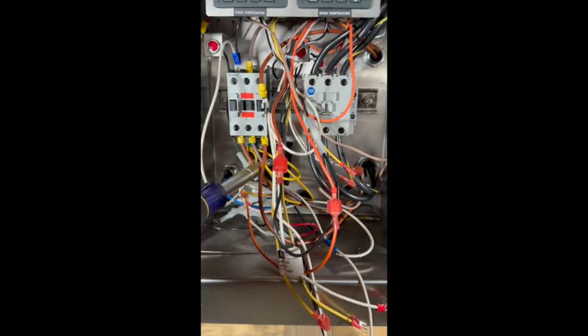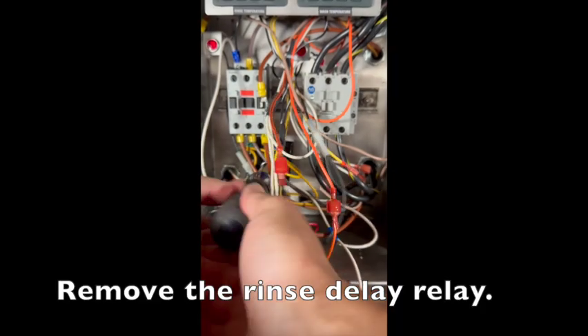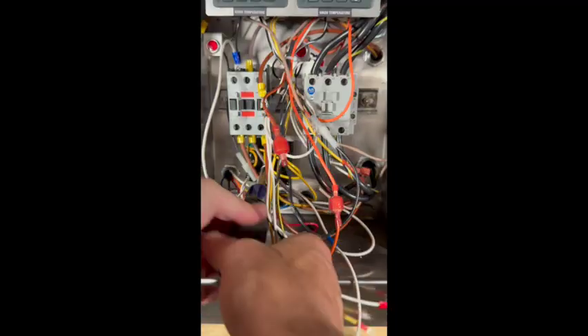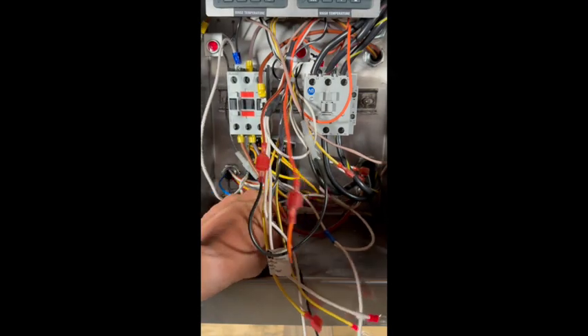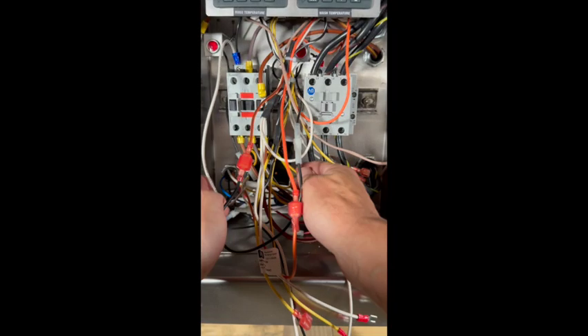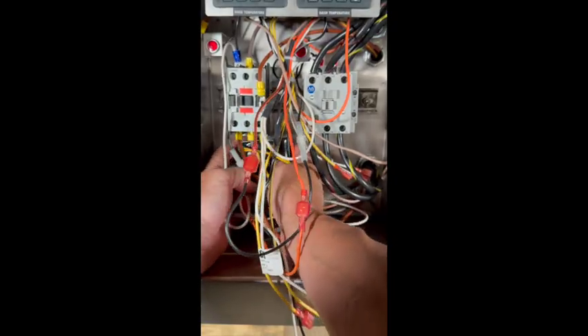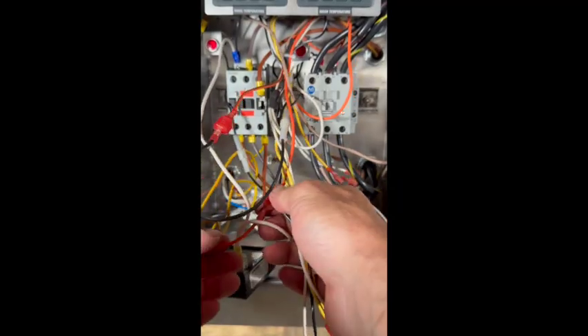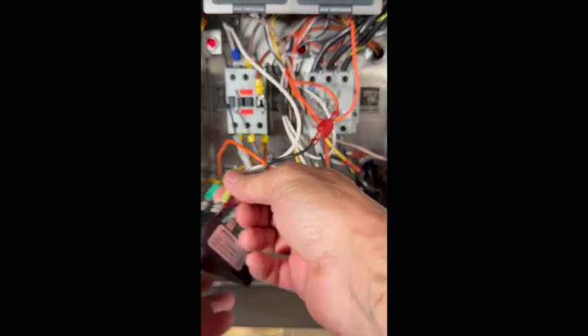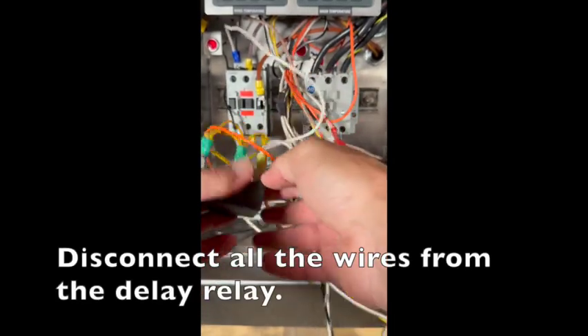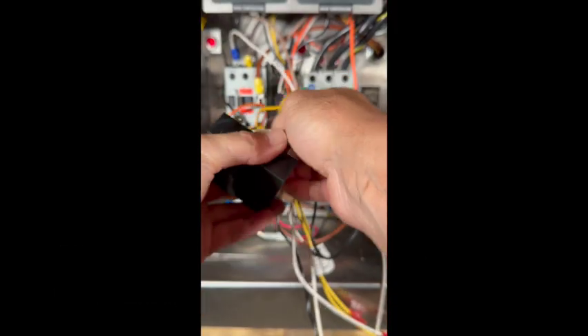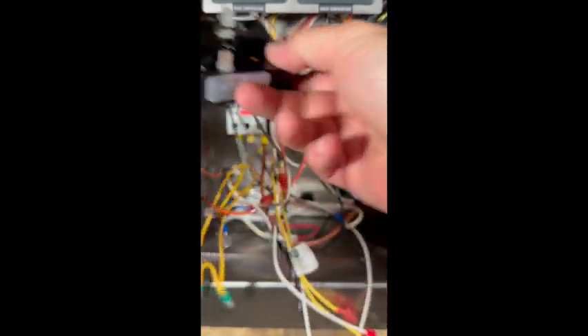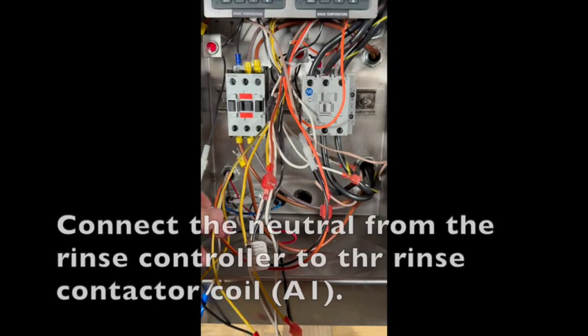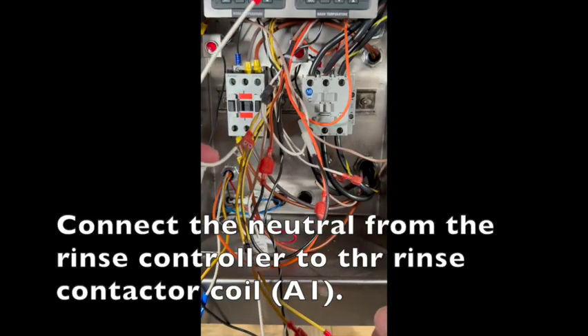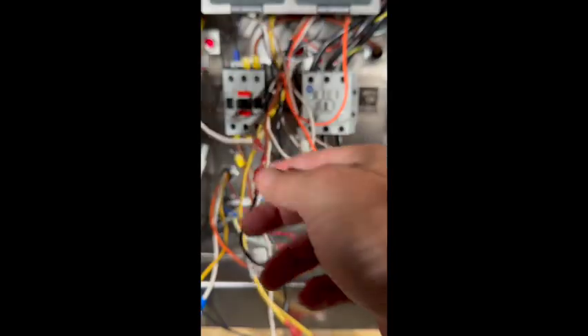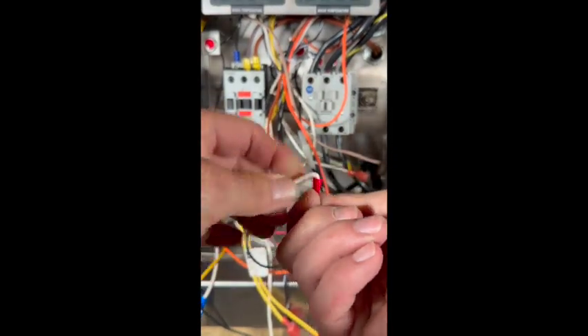We're going to basically do the same thing on the rinse side. Start off by removing the delay relay and all the wires that connect to it. So we're basically going to repeat what we did on the wash side with the rinse. We're going to find the neutral from the controller that's got the forked terminal, and we're going to put that on A1 of your contactor.